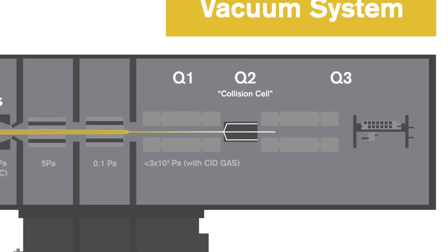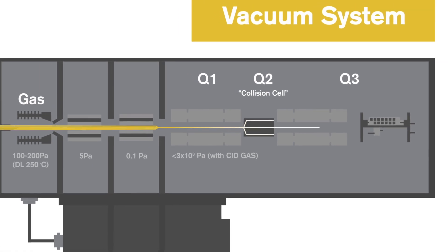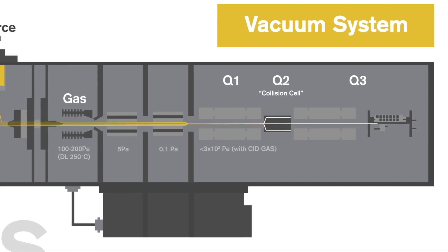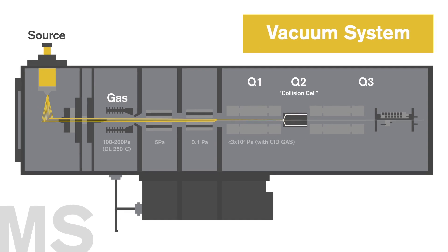The daughter ions are filtered in Q3 and passed to the detector. Each molecule has a unique fragmentation pattern. The mass of the parent and daughter molecules are measured and recorded. The mass of a specific parent molecule and the mass of a daughter molecule are specific, predetermined numbers.